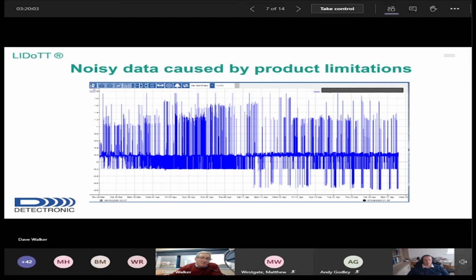That particular application is shown here as a schematic. The actual distance from the ultrasonic sensor to the invert is 2,515 millimeters. Well, this is a 3 meter range ultrasonic level sensor. So it's within range, but it is towards the maximum of its range. When we say 3 meters, we're only within 500 millimeters, if that, of the actual range of that sensor. It should still work. But if you look down on the left-hand side, at the installation sheet on this particular site, it was turbulent.